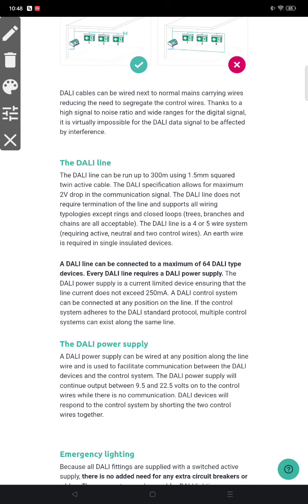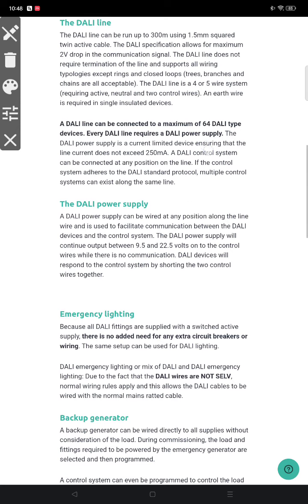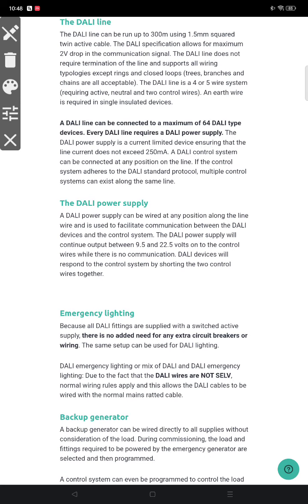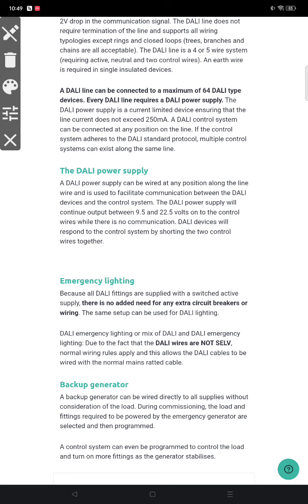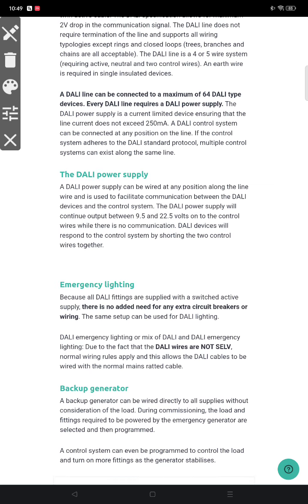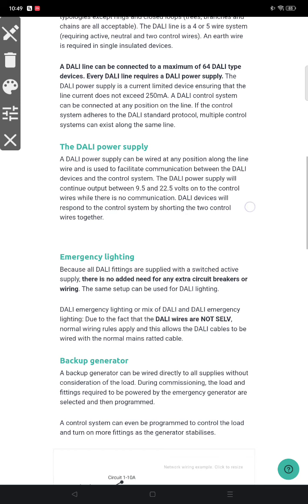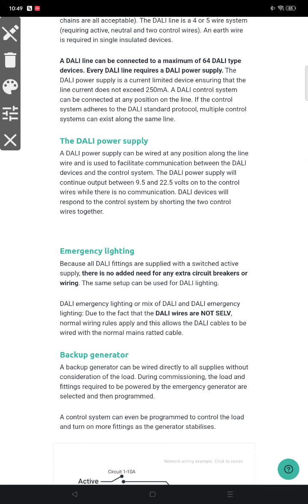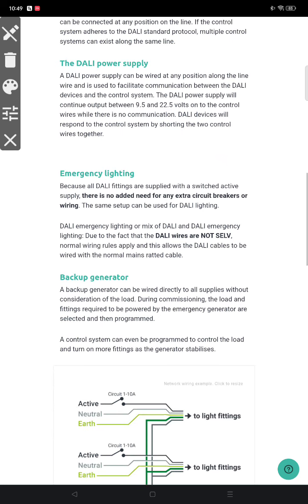The DALI line can be connected to a maximum of 64 DALI devices, and every DALI line requires a DALI power supply. The power supply can be wired at any position along the line and facilitates communication between the DALI device and the control system. The DALI power supply will output approximately 9 to 24 volts on the control wire, and when there is no communication, a DALI device will respond to a control system by shorting the two control wires together.